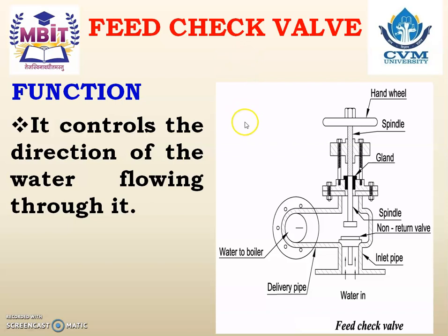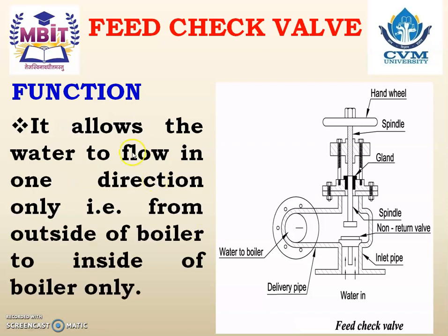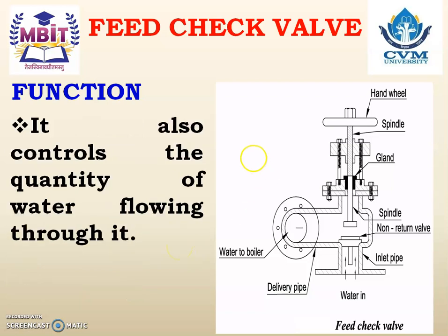The functions of the feed check valve are: it controls the direction of water flowing through it, meaning it allows the flow of water only in one direction — from outside of the boiler to inside of the boiler only. It also controls the quantity of water flowing through it, meaning how much water should pass is also controlled with the help of the feed check valve.